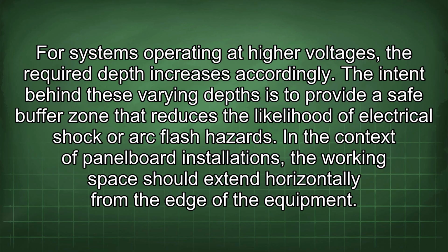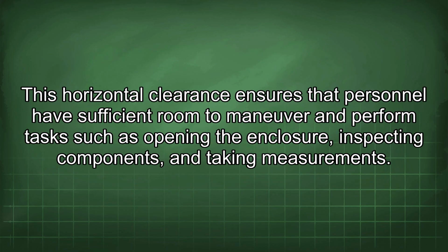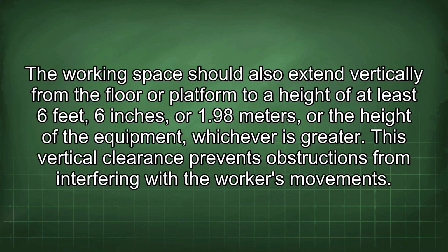In the context of panelboard installations, the working space should extend horizontally from the edge of the equipment. This horizontal clearance ensures that personnel have sufficient room to maneuver and perform tasks such as opening the enclosure, inspecting components, and taking measurements. The working space should also extend vertically from the floor or platform to a height of at least 6 feet 6 inches, or 1.98 meters, or the height of the equipment, whichever is greater. This vertical clearance prevents obstructions from interfering with the workers' movements.